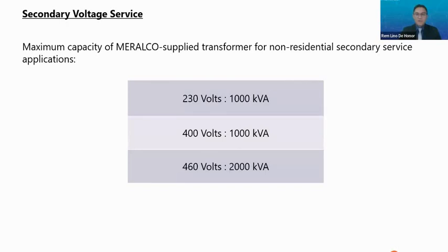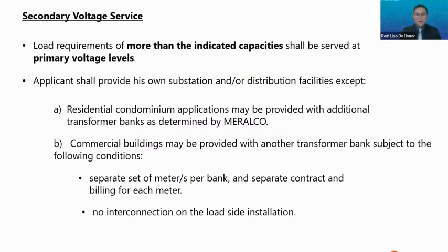These are the maximum capacities of the Meralco supply transformer for secondary service. For 230 volts and 400 volts, the maximum capacity of the Meralco supply transformer is 1000 kVA. And for 460 volts, the maximum capacity is 2000 kVA. Load more than the indicated capacity shall be served at primary voltage levels. The applicant shall provide his own substation or distribution facilities, except that residential condominium applications may be provided with an additional transformer bank as determined by Meralco. This is subject to evaluation by engineers.